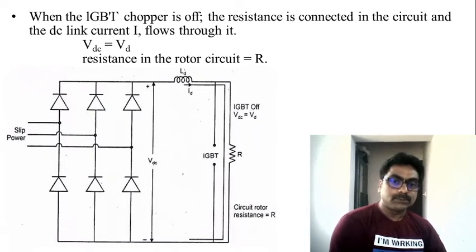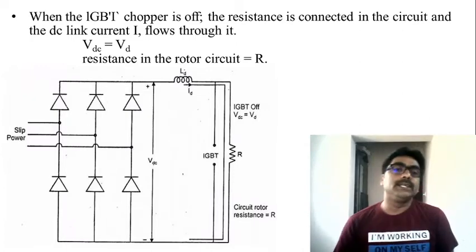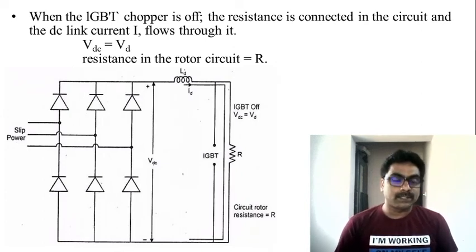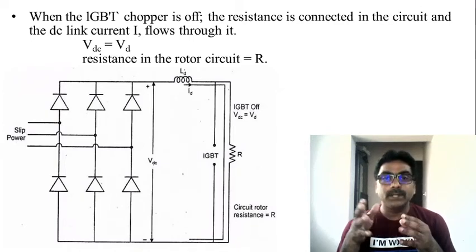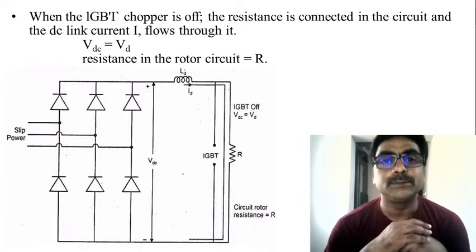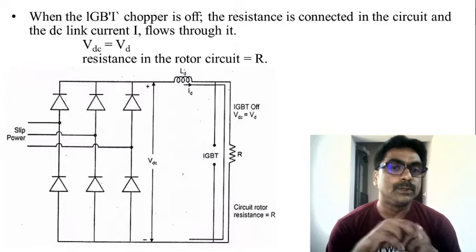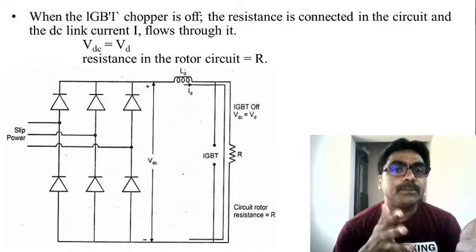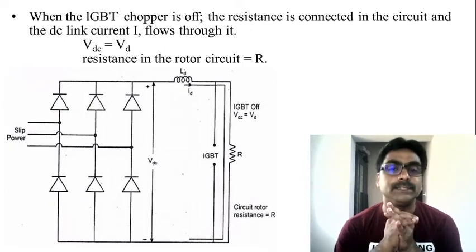When the switch is OFF, the current flows through the resistor and the voltage that appears across the diode rectifier output appears across the resistor. Here the rotor resistance is now equal to R — the resistor we are connecting across the circuit. The total resistance is R, and the voltage across the resistor is V_DC, so V_D equals V_DC.